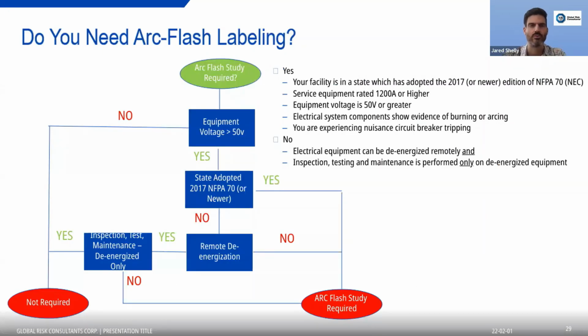And I want to put this on the screen as well. Do you need arc flash labeling? This is a very, very high level grid structure that can help you answer that question. Basically, if your facility is in a state that adopted the NFPA 70E from 2017 or more recently, if your equipment is rated 1200 A or higher, if the voltage is 50 volts or higher, you're experiencing nuisance circuit breaker tripping, or electrical system components show evidence of burning or arcing, then yeah, you do need to assess that and make sure that your labels are right, and more importantly, make sure that your whole system is right. So I wanted to just put this on the screen so that folks have it if they reference this later.